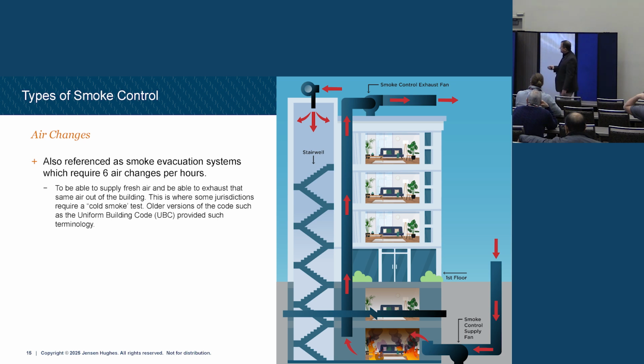And again, lots of sequence of operations here, right? I've got inputs that turn all this on, and then I've got this fan, this fan, this fan. They all work differently based on the floor. There's a lot of complexity here. But this was common in the Uniform Building Code, which is a legacy older code that predated the International Building Code. Was pretty common, and you used a cold smoke test to test for it.